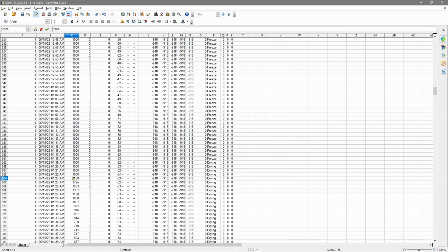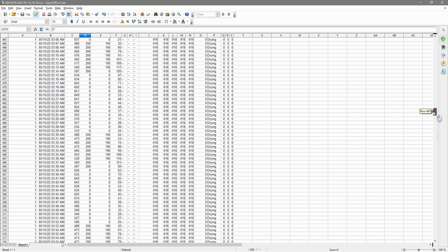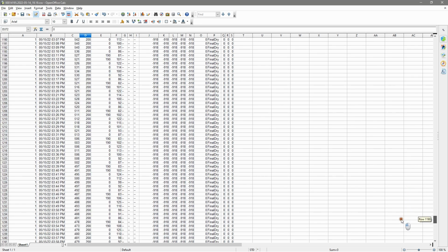Like I said, it would hide a trouble. It would hide a vacuum problem if you had that, so you wouldn't do that if that's what you're looking for. But by doing this, it keeps the scale lower, and then it's easier to watch the rise and fall of the temperature. It only changes about 6 minutes worth. There'll be a few more of them, so when I open the drain valve, they'll have the same thing at the other end. And when I restart, where is that?